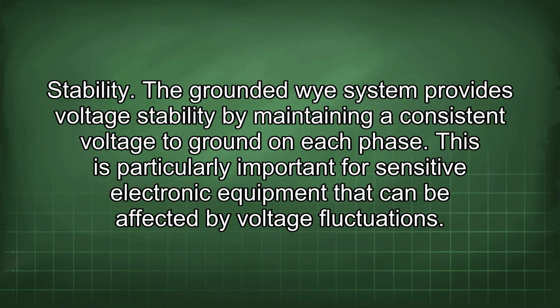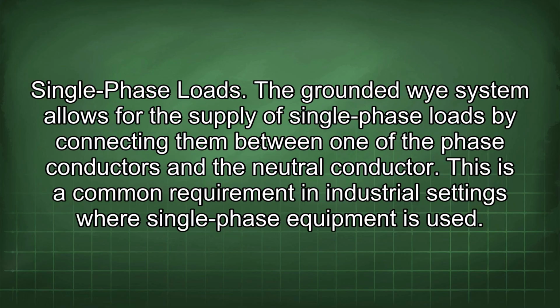Sixthly, advantages of grounded Y secondary. Stability. The grounded Y system provides voltage stability by maintaining a consistent voltage to ground on each phase. This is particularly important for sensitive electronic equipment that can be affected by voltage fluctuations. Single-phase loads. The grounded Y system allows for the supply of single-phase loads by connecting them between one of the phase conductors and the neutral conductor.